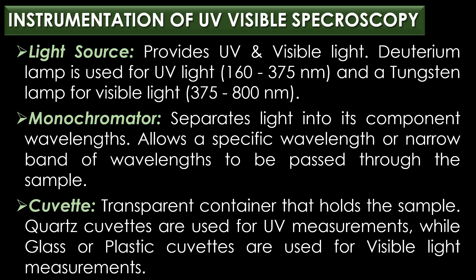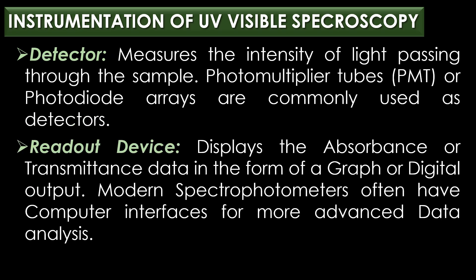Third, a cuvette is a transparent container that holds the sample. Quartz cuvettes are used for UV measurements while glass or plastic cuvettes are used for visible light measurements. Fourth, the detector measures the intensity of light passing through the sample; photomultiplier tubes or photodiode arrays are commonly used as detectors.